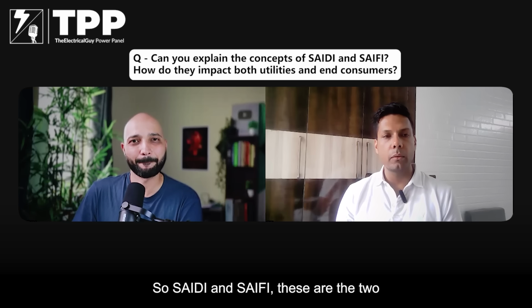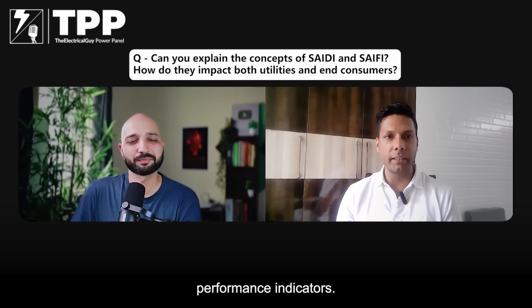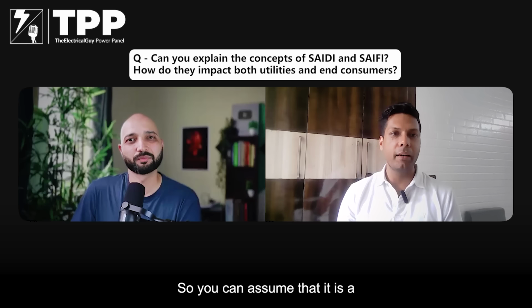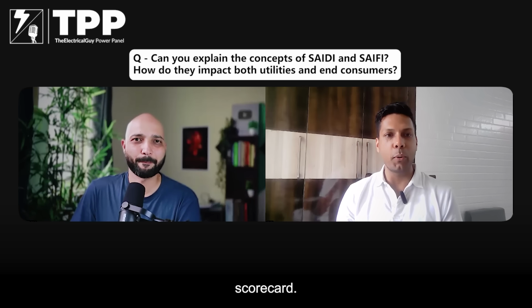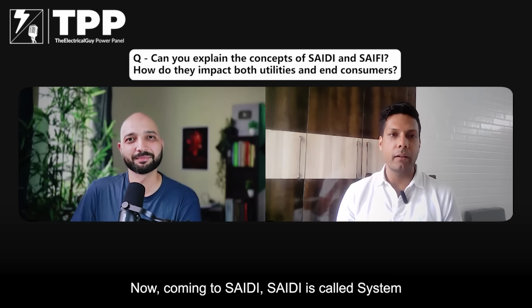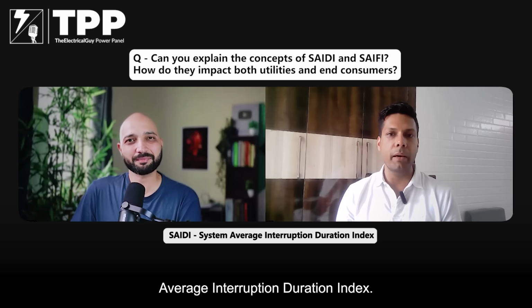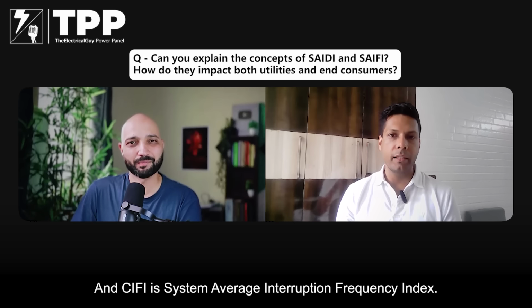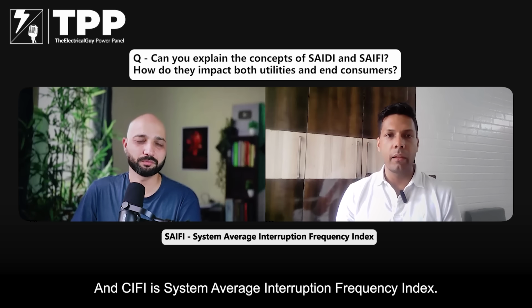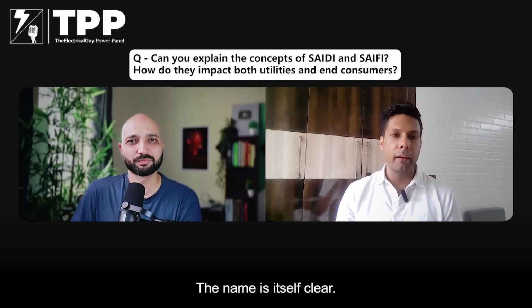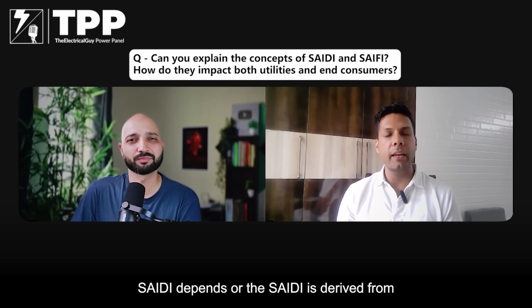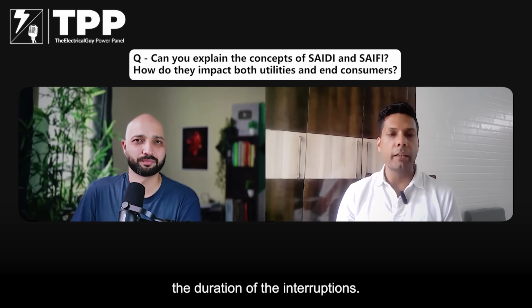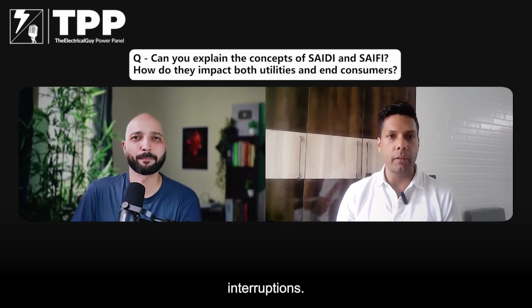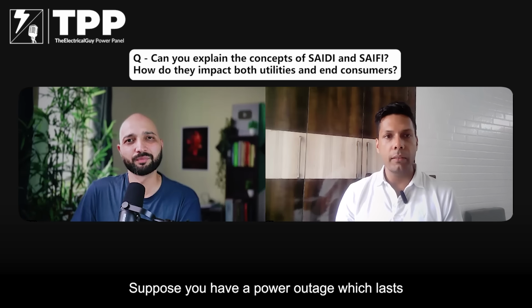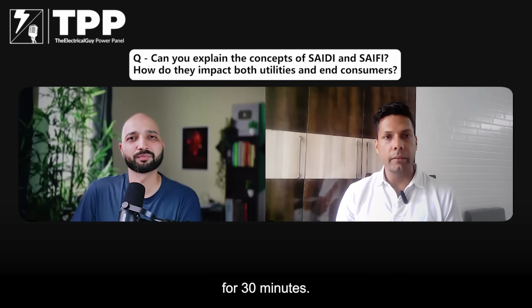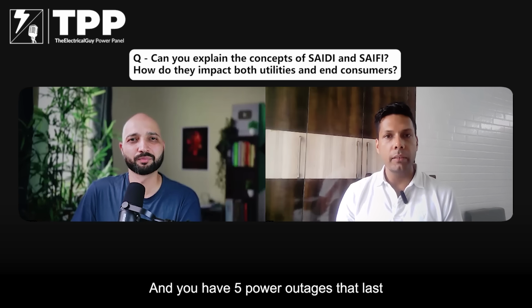Yeah, absolutely. So SAIDI and SAIFI are two performance indicators. You can assume that it is a kind of score that you get in your scorecard. Now, coming to SAIDI, SAIDI is called System Average Interruption Duration Index, and SAIFI is System Average Interruption Frequency Index. The name itself is clear. SAIDI is derived from the duration of the interruptions, and SAIFI is derived from the frequency of interruptions.